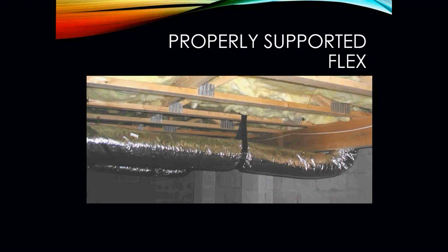Notice in this picture how straight that ductwork is. We do not want to have sags. We do not want to have any sort of sharp bends when we are dealing with flexible duct. That will create friction loss. It's going to slow down the air velocity traveling through that. When we are installing ductwork, we want to try to keep it as straight as we possibly can, with few bends. And if we have to put a bend in it, we want to keep it a gradual, nice swoop, so that we don't have turbulence and we don't have air velocity issues in spaces.